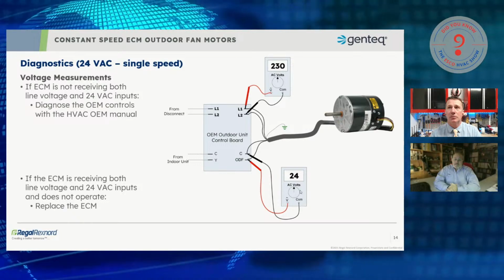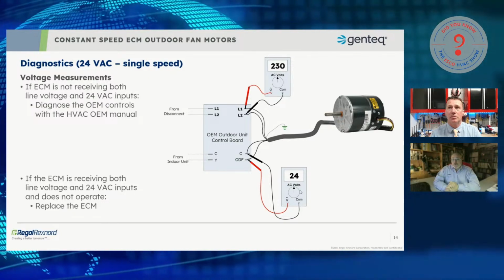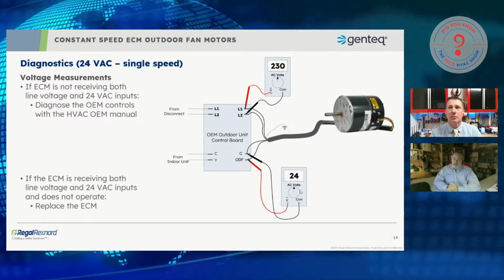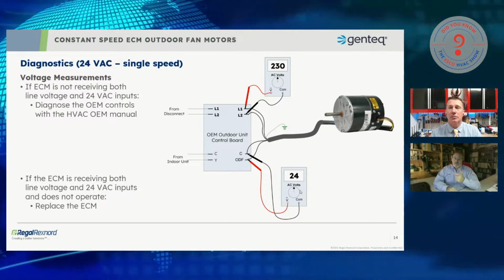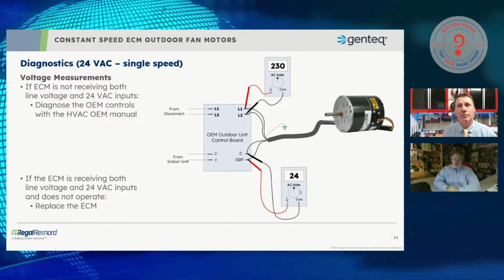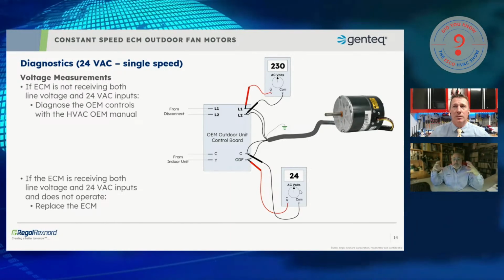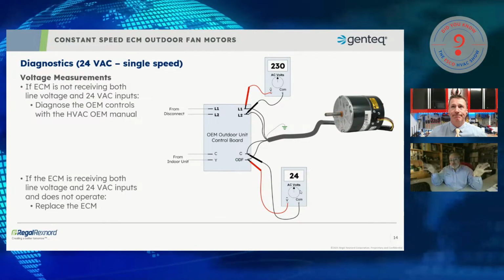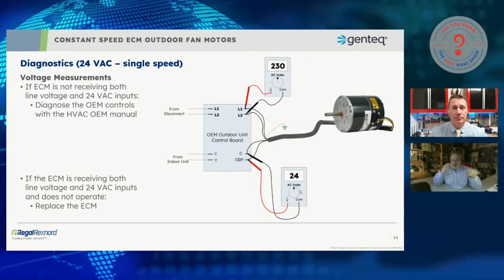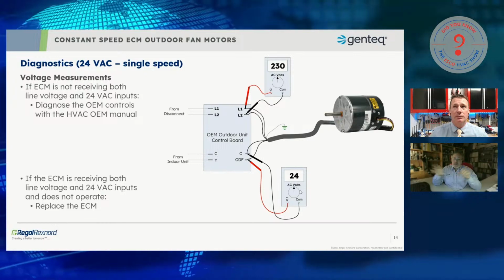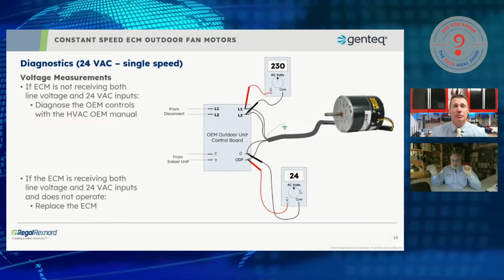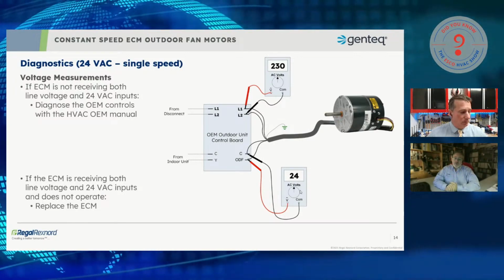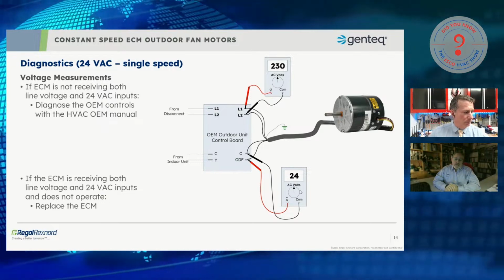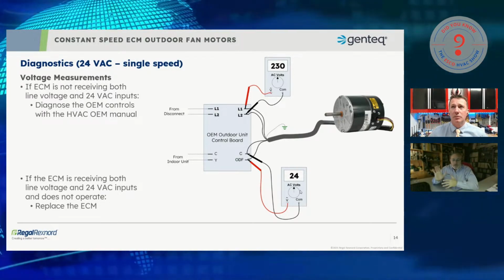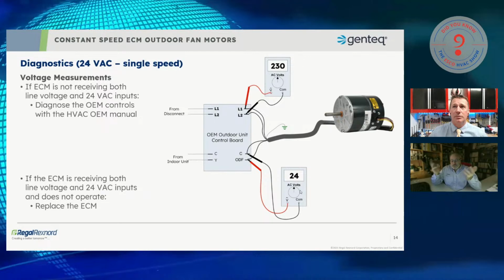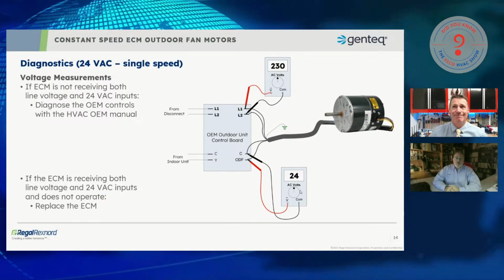And the easy answer to that is you can if you want to, but I don't know of any OEMs that are selling the control-only replacement today in the outdoor fan motor. To my knowledge, they're all selling it as one complete part. Even the remote located ones, where the motor's remote located from the control, they still only sell it as one complete system, the motor and the control. So ohming out the motor is really a waste of your time, unless you just want to know which came first, the chicken or the egg? Did the control or the motor fail?